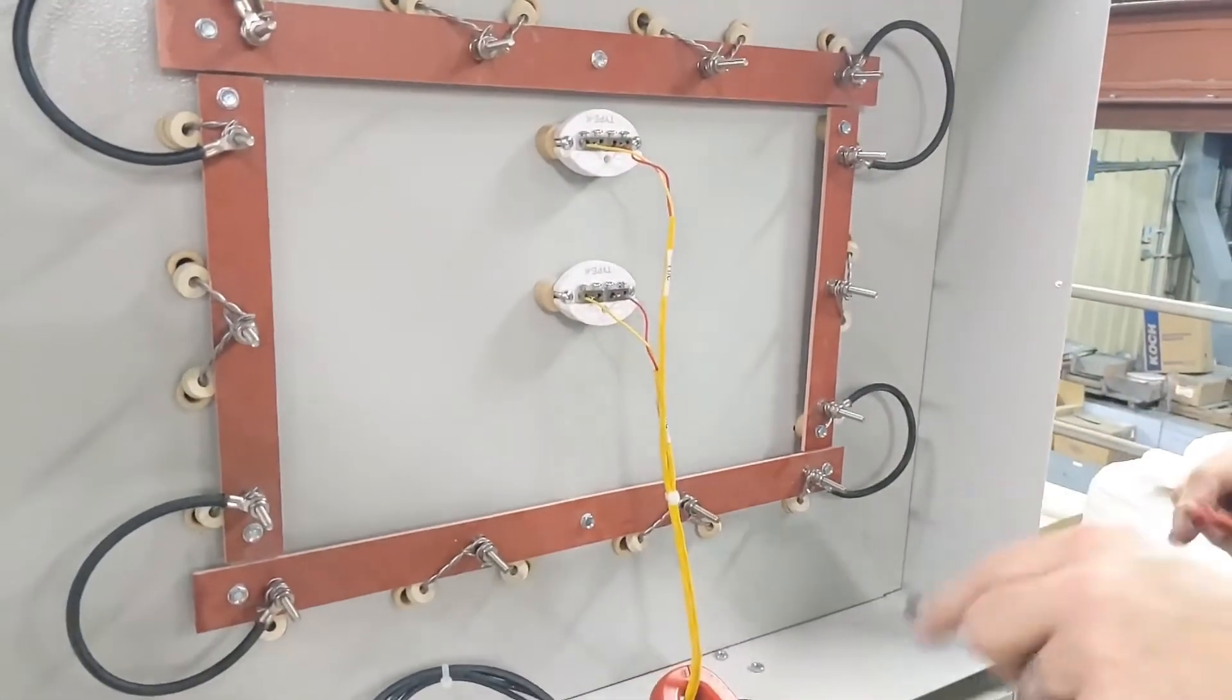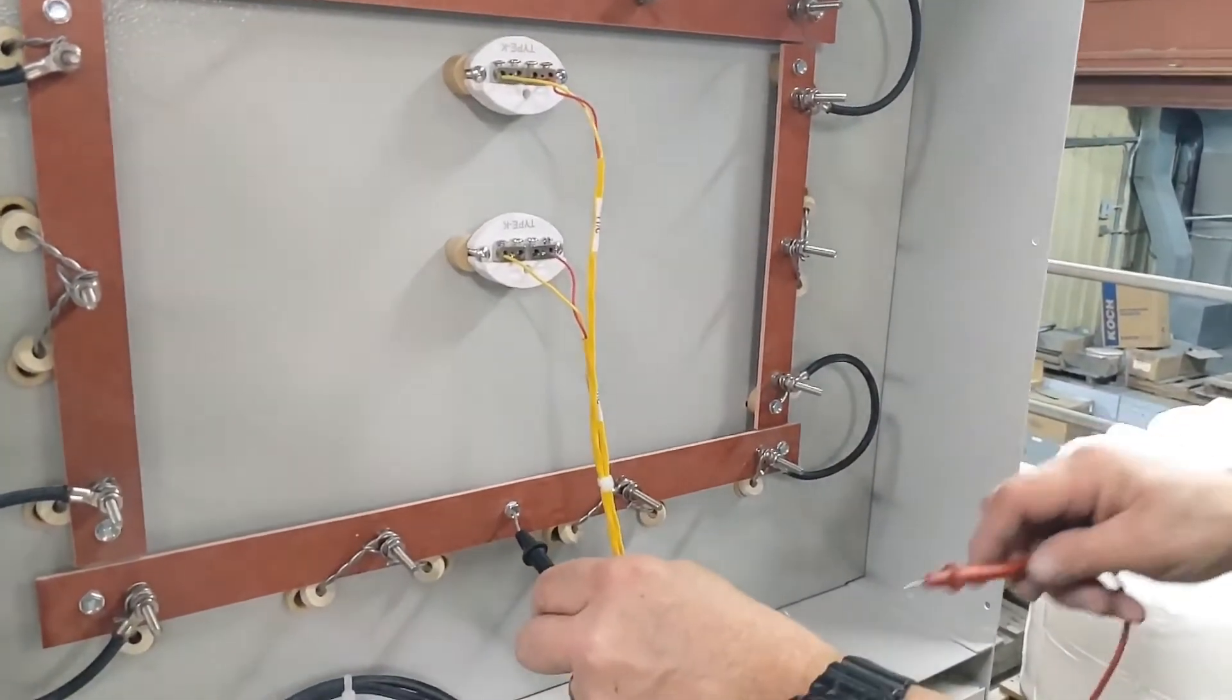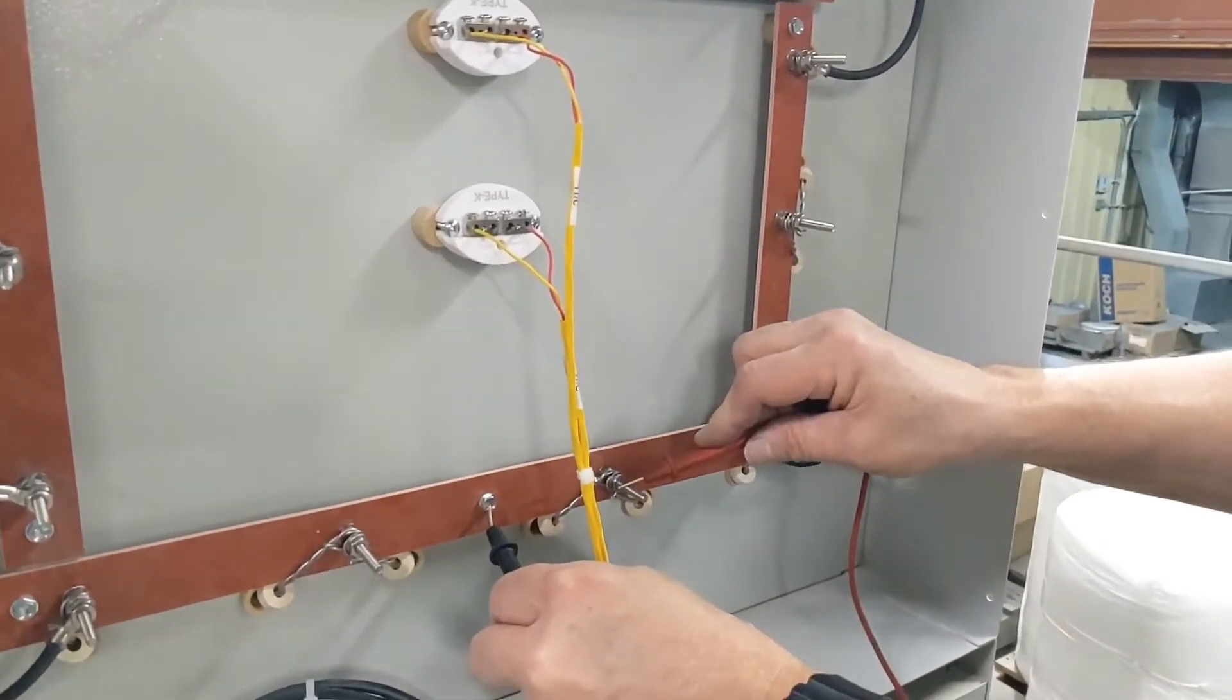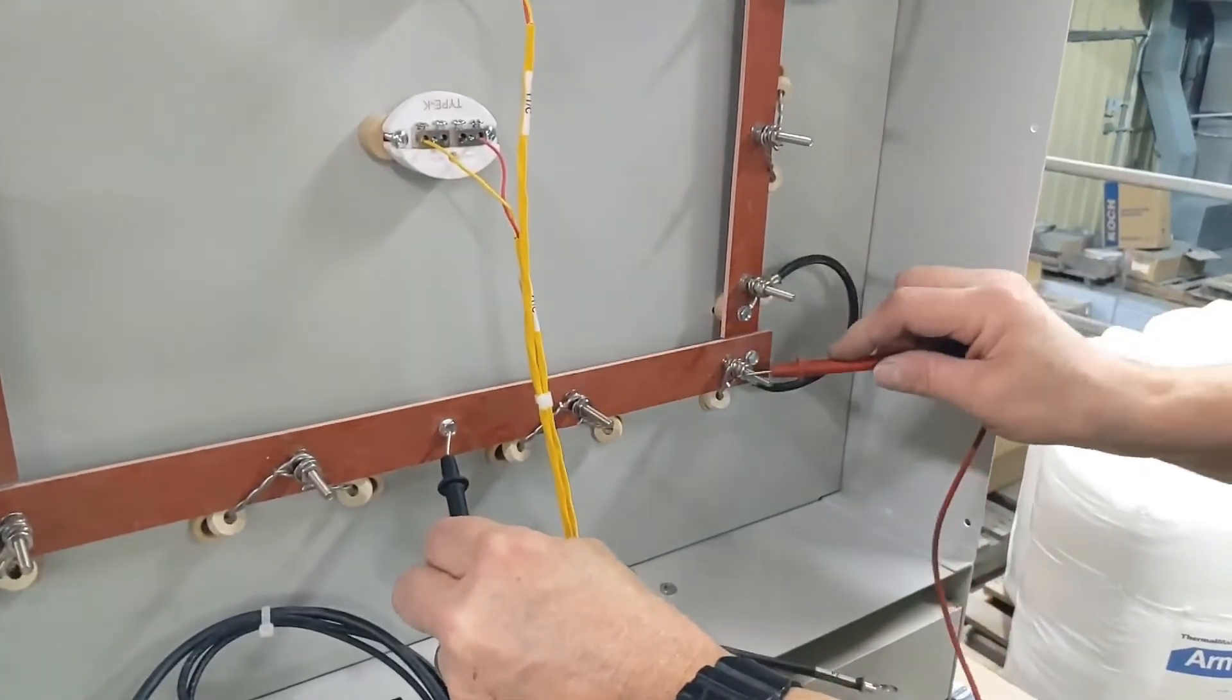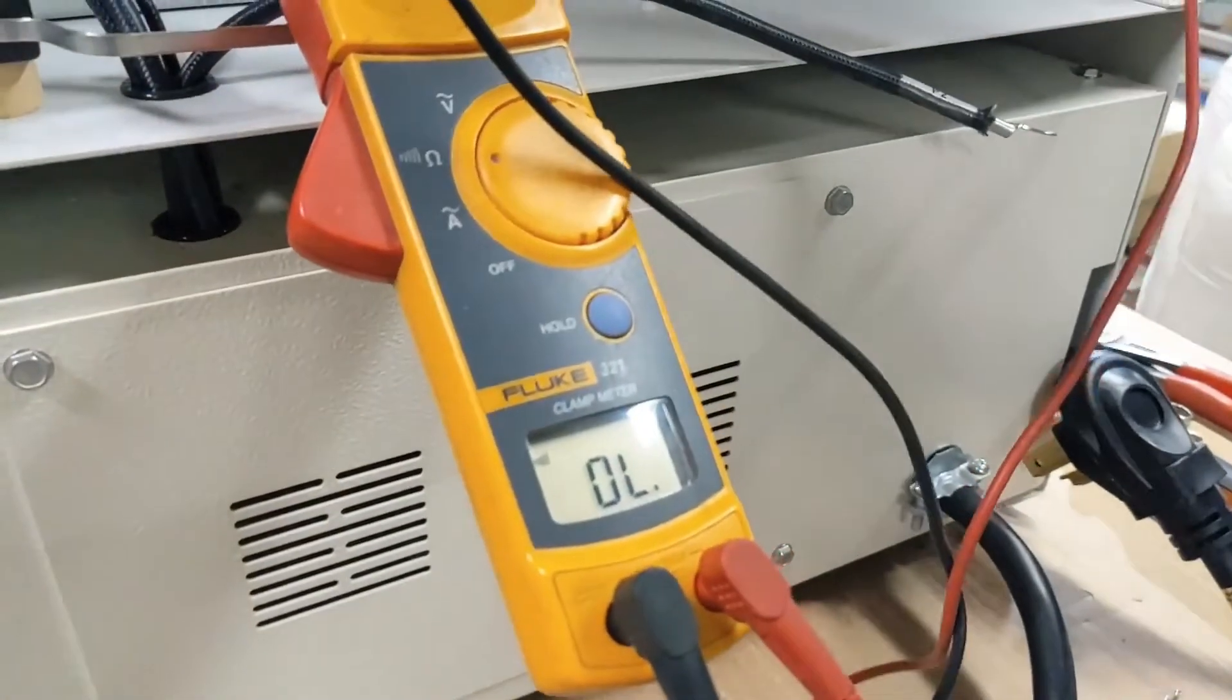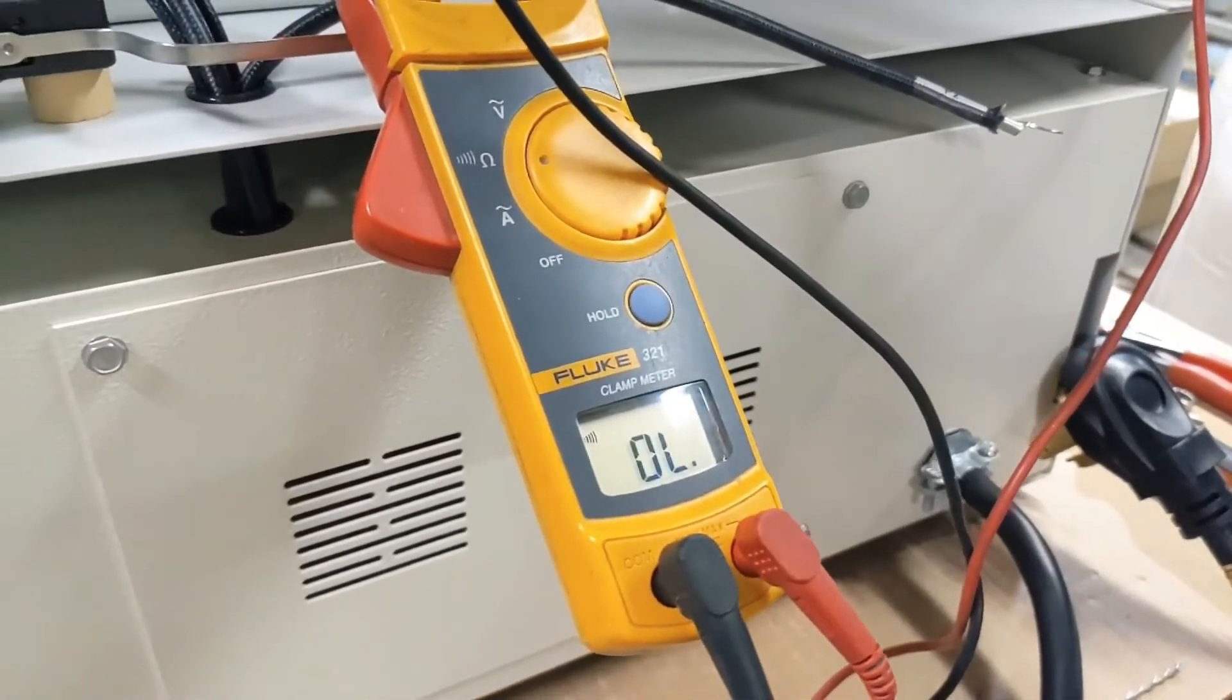The next step is to check resistance to ground to make sure no element is touching the metal case. We want to go from the element terminal to the mounting bolt for one of the terminal boards. And these should be an open loop.